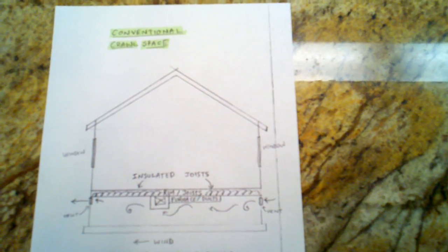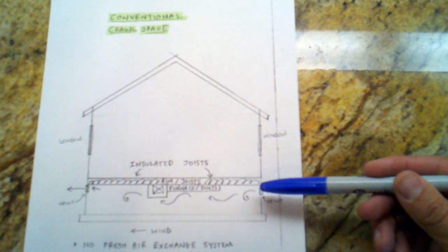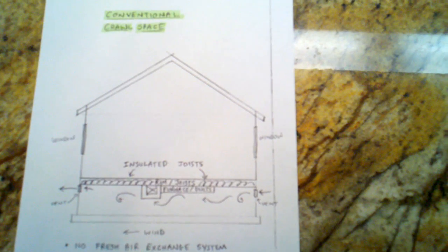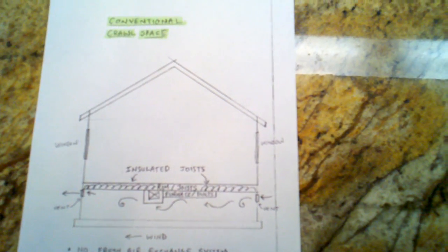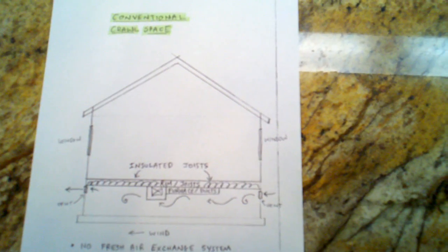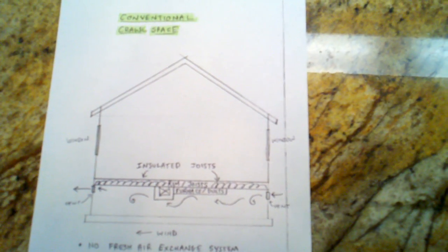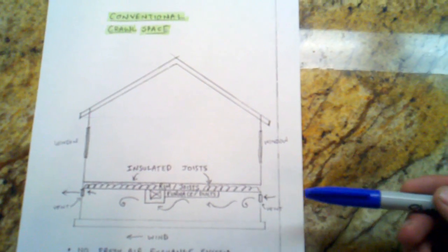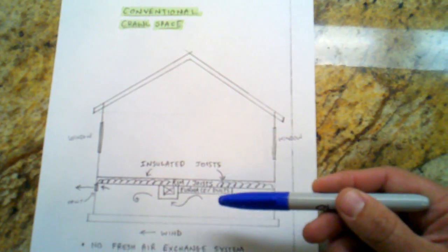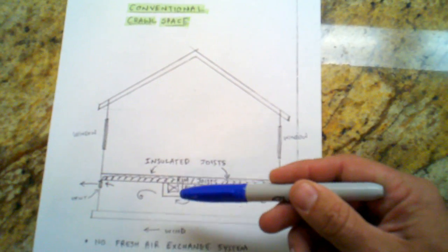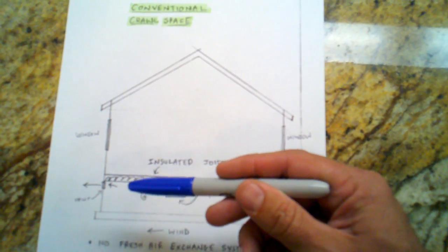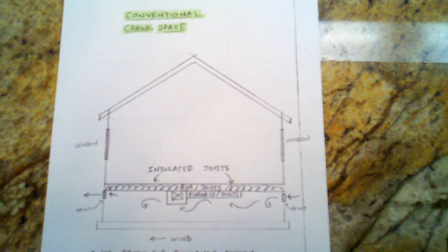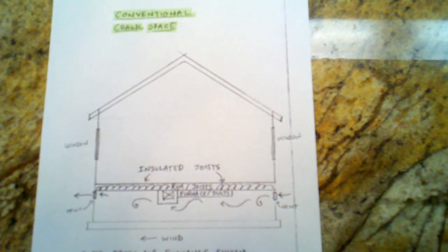And the way that this is typically vented is with vents in your stem wall or in the rim joist. You'll see it different ways, which in our opinion does not look that aesthetic from outside, but functionally I'll go through the main functional detriments to doing your crawl space this way. So let's say the wind is blowing from the right. It goes in this vent into the crawl space, blows around, circulates around your furnace and your ducts, picks up any moisture and radon gases, and allegedly vents those out the windward or the leeward side, like you see here.